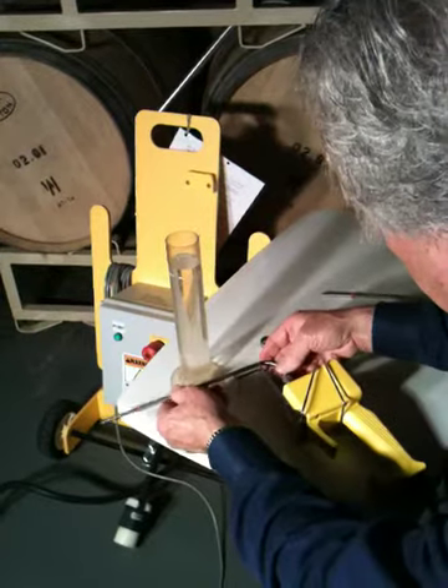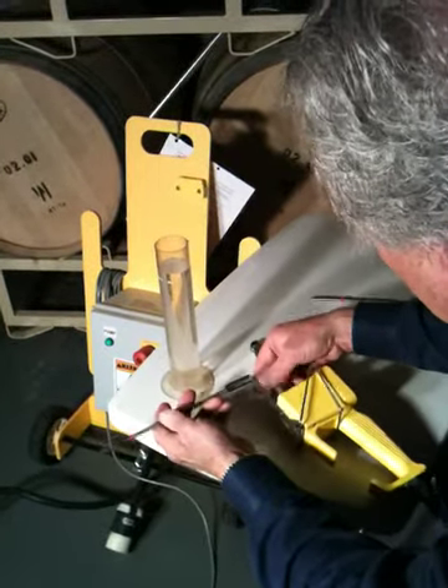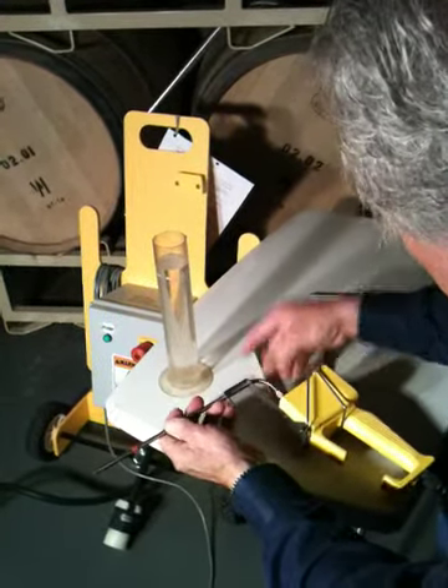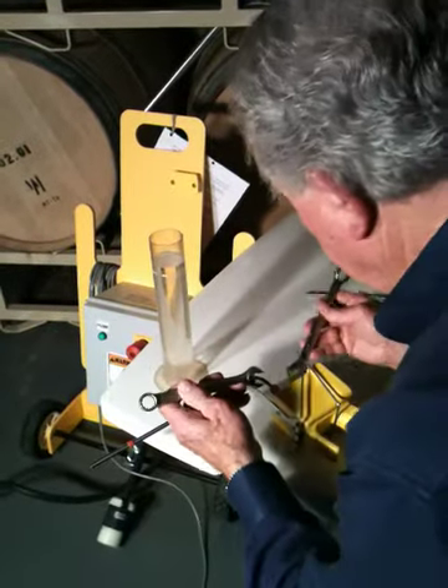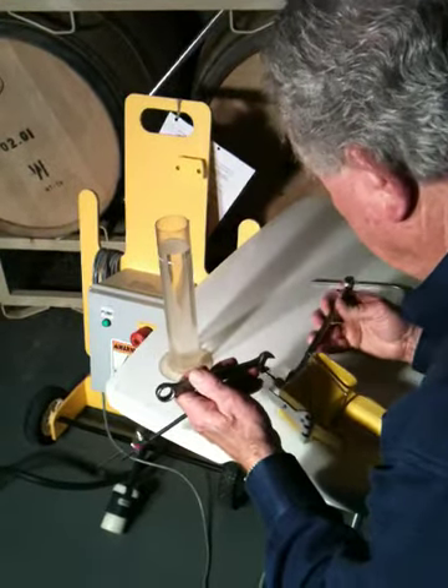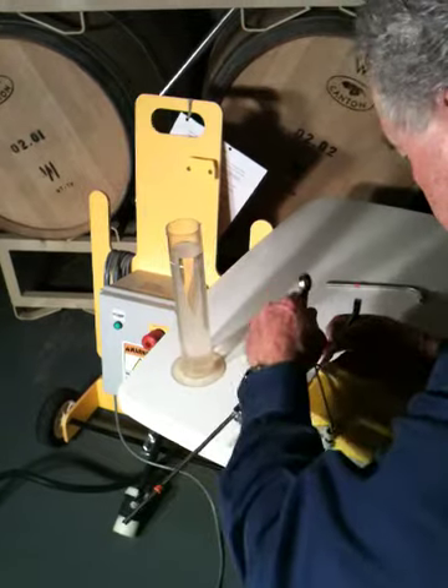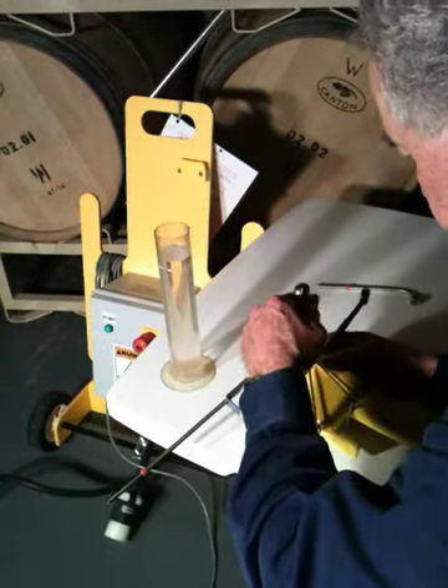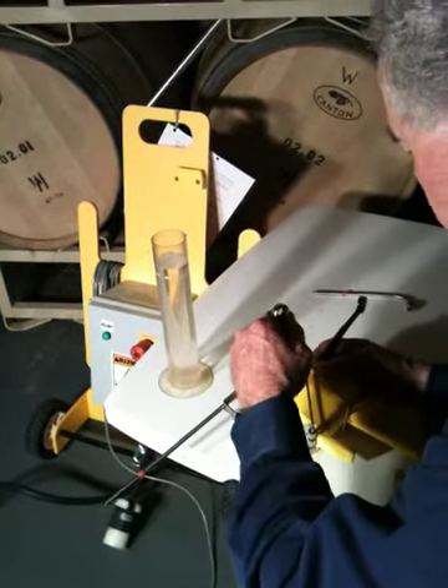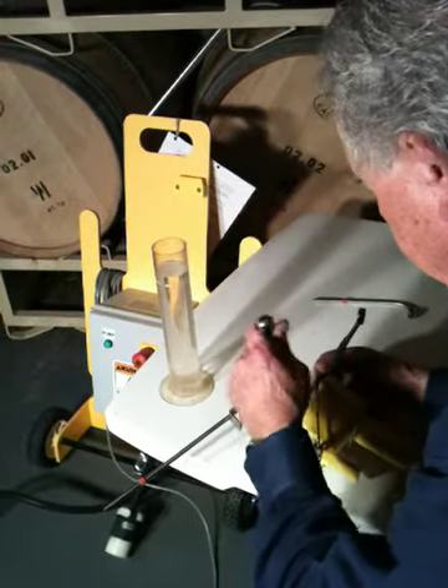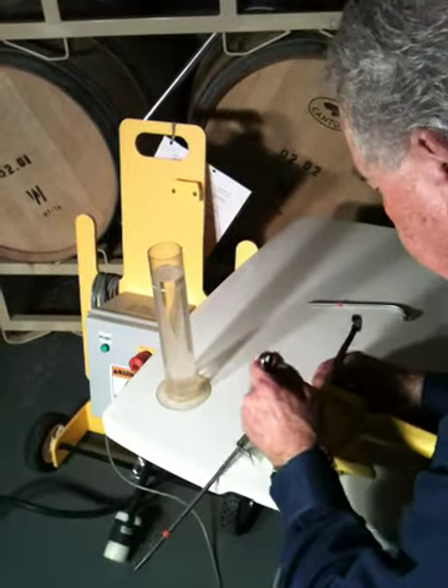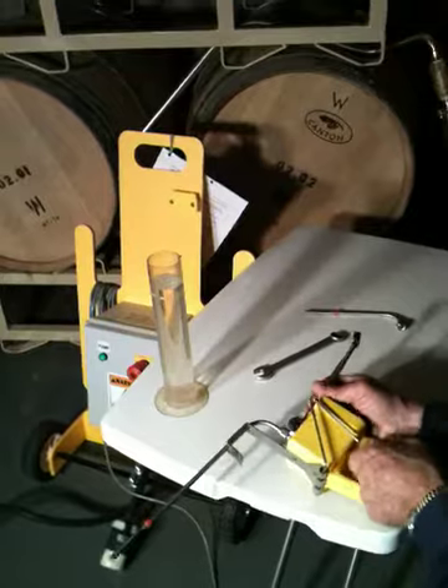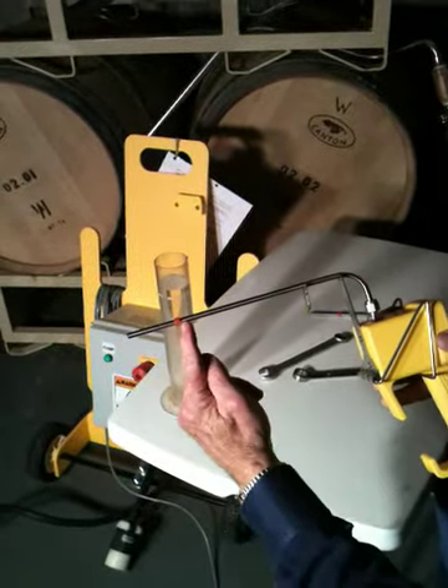So we put it in, turn it on by hand, and then we tighten it. This is a critical part here. Make sure you've got it tight, because if you don't, you're going to have a leak. And this tube, it is recommended strongly from the factory that you take this tube off and clean and dry it after each day's use, each barrel filling session. There it is.